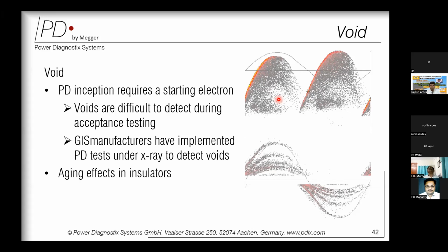The next action that can be initiated is to use an instrument with a temporary monitoring feature and put it on those channels where you are observing PD, for trending over a period of, say, a week, 10 days, or a month. If you are getting consistent partial discharge results, then the next step is to really take a decision and move forward, that yes, these are serious partial discharge patterns and I should take some action so that the reliability of the GIS is not disturbed.